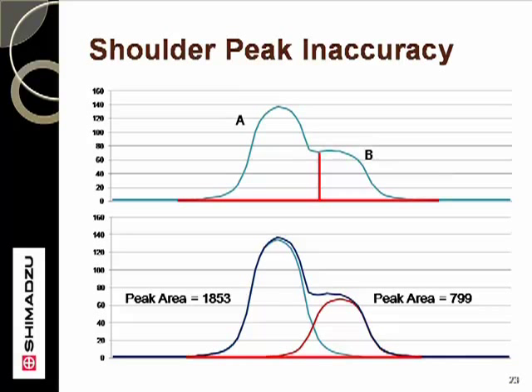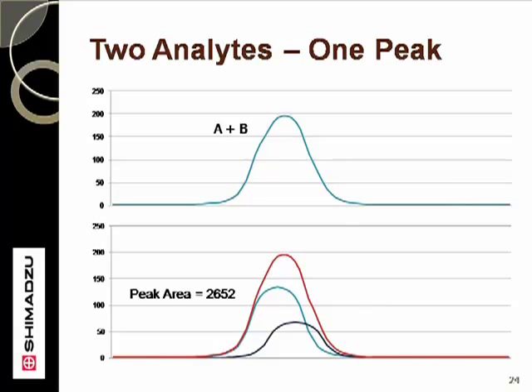When the peaks begin to move closer, it is possible for the smaller component to lose much of its identity. The smaller peak becomes more of a shoulder on the side of the larger peak. Processing is also done by splitting the shoulder from the larger peak, but there may not be a defined valley to use as a processing point. In the example shown, the minimum point of the shoulder was used as a splitting point, and the peak areas add more to the A component — 1853 instead of 1780 — and less to the B component — 799 instead of 872. This inaccuracy in the assignment of peak areas is a consequence of not getting better peak separation. Moving the two peaks closer together does result in a single peak, though it may start to look even more misshapen. The peak areas are fully additive, but it is not realistic to get a value for each component.